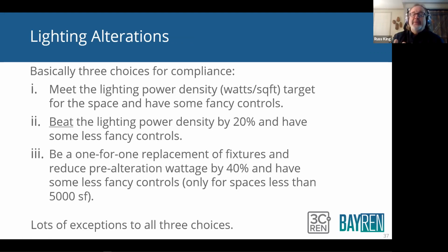So here's your three choices. They give you three options to meet the requirements. Let's say you're replacing all the fixtures in a room, okay, or most of the fixtures. How do you meet the requirements? The first one is to meet the lighting power density and have some controls, okay, some special controls. So the lighting power density is watts per square foot. That is sort of what the industry has decided is a reasonable level of lighting for that type of occupancy, whether it's office space, whether it's retail space, whether it's a gymnasium, you know, whether it's a meeting room.